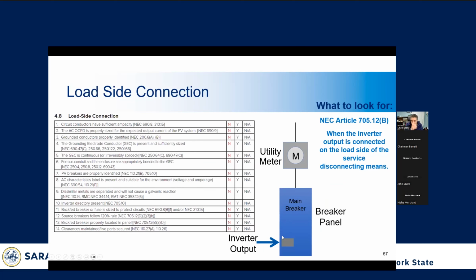Now we're going to start talking about the interconnections. This is kind of a simple drawing of where a load side interconnection is made. This is where the inverter output is connected on the load side of the service disconnecting means, which is typically a backfeed breaker or a sub panel. And so these are typically located on the opposite side of the panel from where the utility power is coming in. This is so that you don't overload the bus bar within the panel.